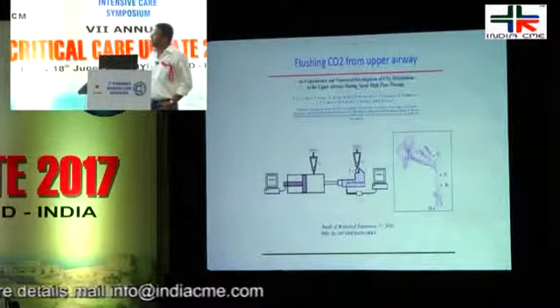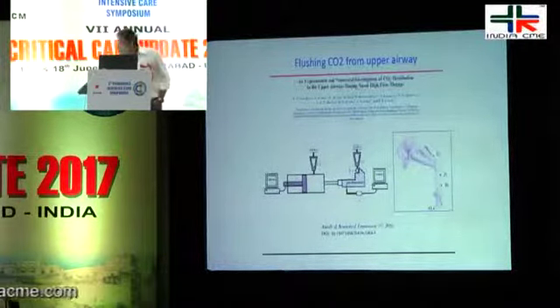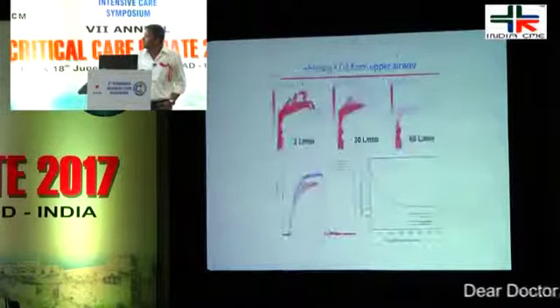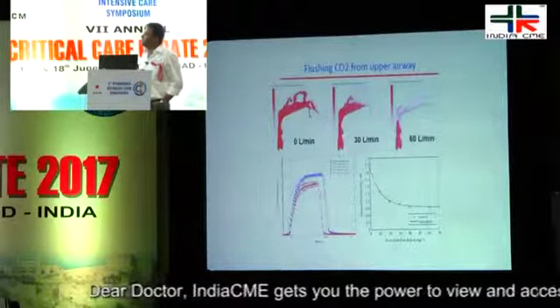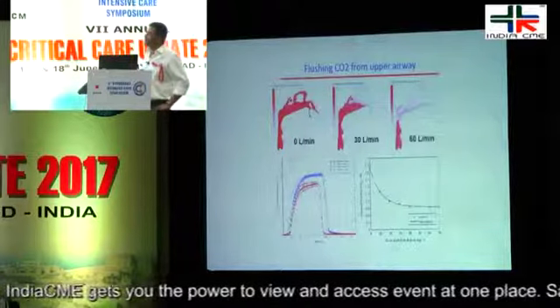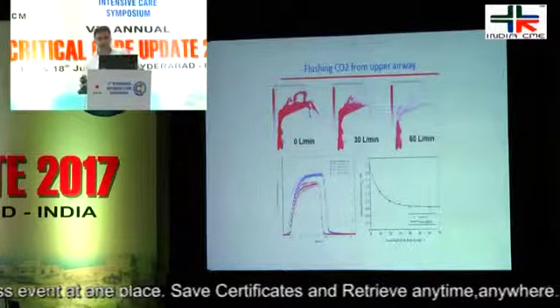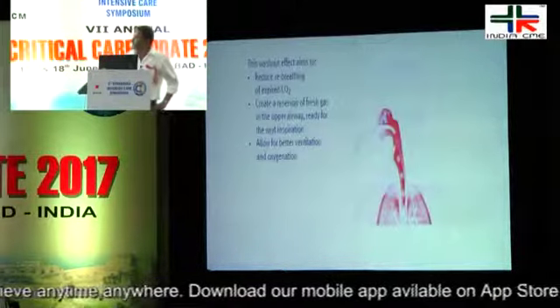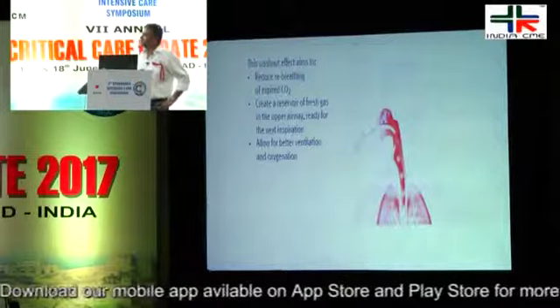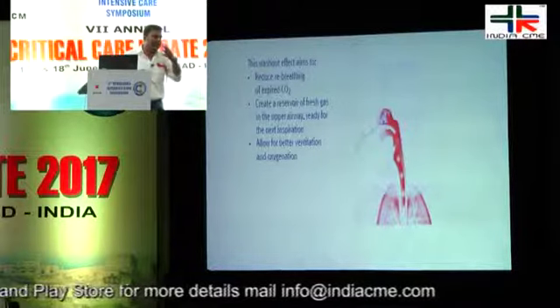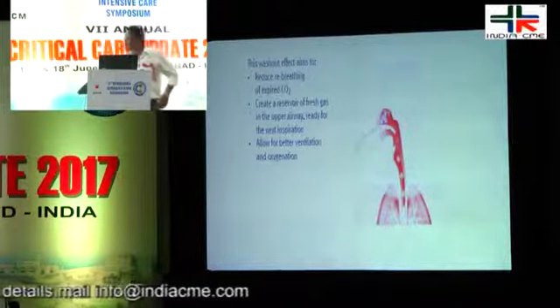Also, this high flow of air movement or oxygen movement flushes carbon dioxide from the upper airway. And you can see in this experiment, this is the no flow state, this is where there is a 30 liter per minute flow, and this is a 60 liter per minute flow, and the red color is the accumulated carbon dioxide in the upper nasal airway or the upper airway, right. So a good amount of carbon dioxide washing is happening, and this washout effect reduces the rebreathing of expired CO2, as well as it creates a reservoir of oxygen inside. So that means it is increasing your delivered FiO2 and allows better ventilation and oxygenation.